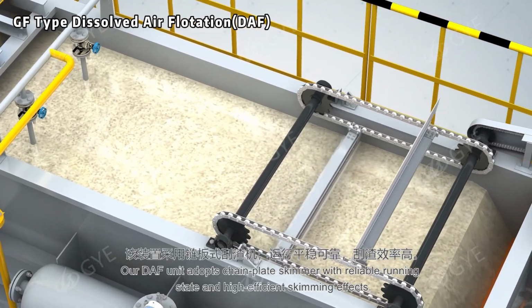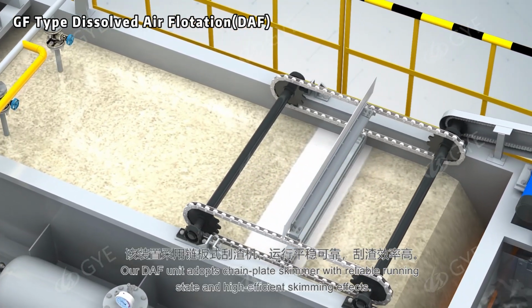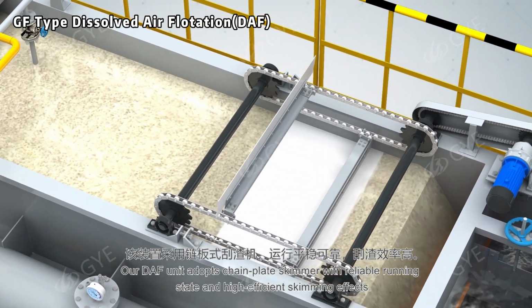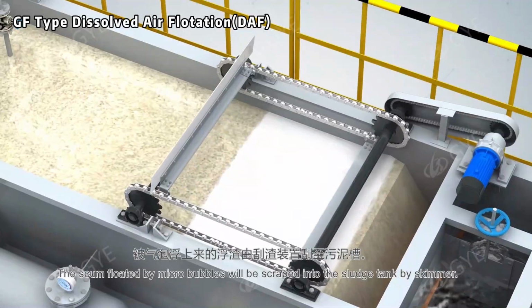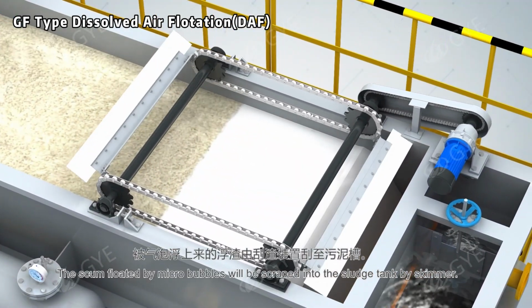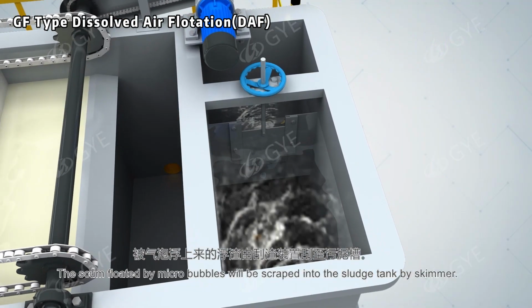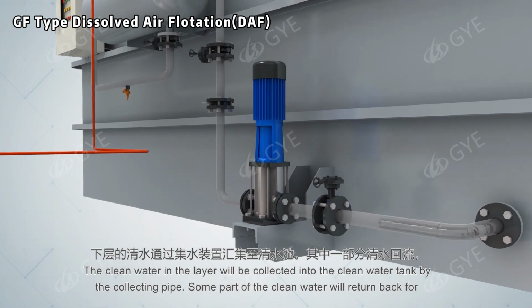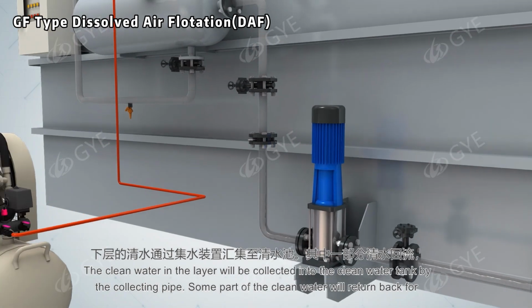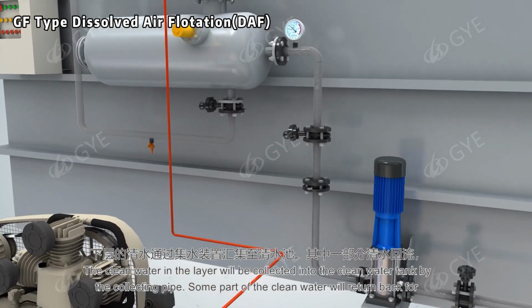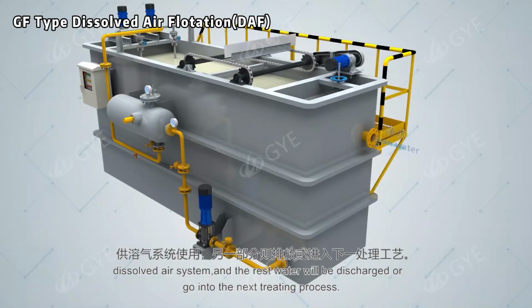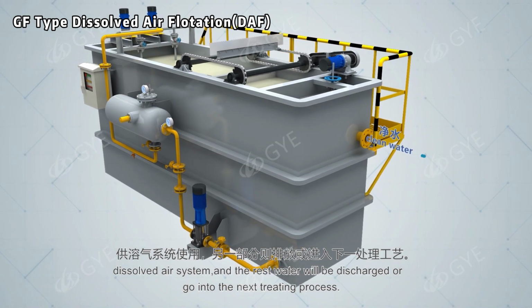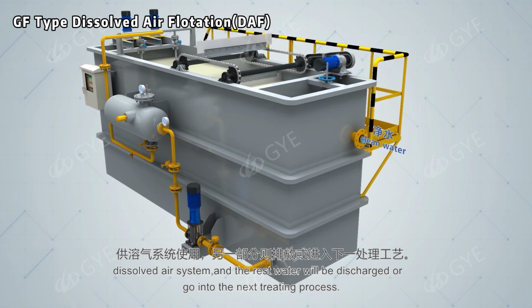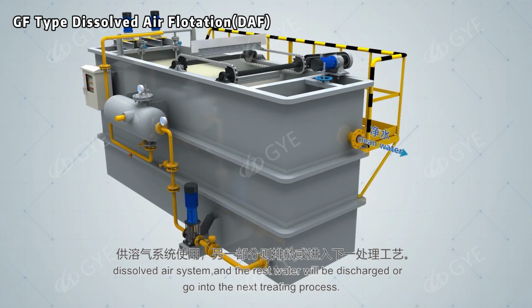Our DAF unit adopts chain plate skimmer with reliable running state and high-efficient skimming effects. The scum floated by microbubbles will be scraped into the sludge tank by skimmer. The clean water in the layer will be collected into the clean water tank by the collecting pipe. Some part of the clean water will return back for dissolved air system, and the rest water will be discharged or go into the next treating process.